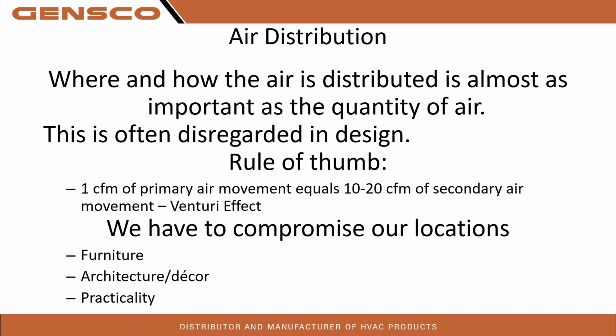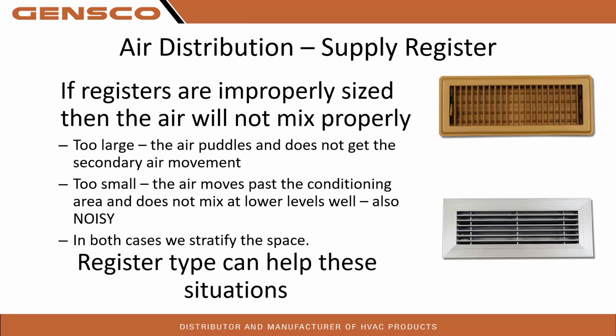They used to have all the supplies on the interior of the room and the returns on the exterior. Now we've had the returns on the interior of the room and supplies on the exterior. So know where your supply and returns are. Of course, these registers with the dampers, people are always thinking they're not going to heat that room, so they're going to close that up. Be aware that's going to increase static pressure and could possibly lead to discomfort. So when we're starting up the system, make sure we've got all the registers open. Let people know, don't close up too many because that's going to create an issue.